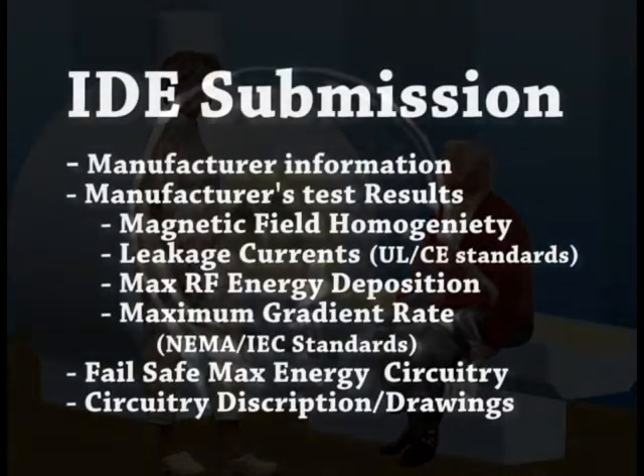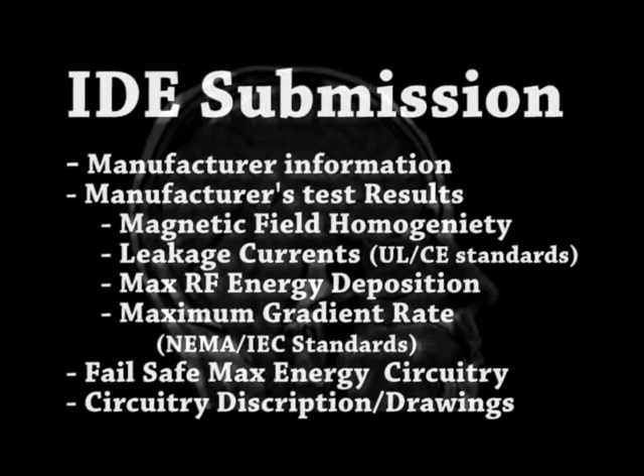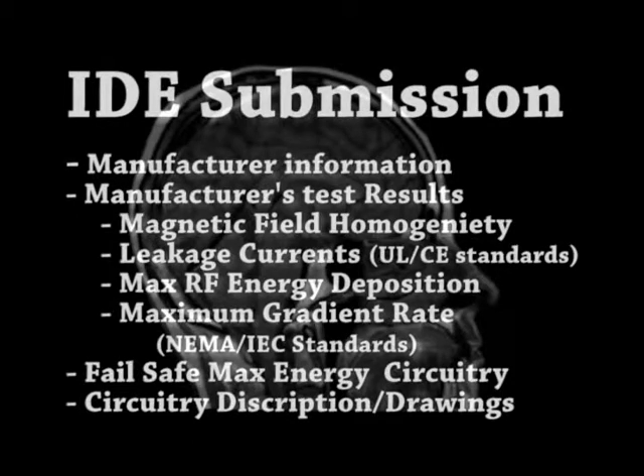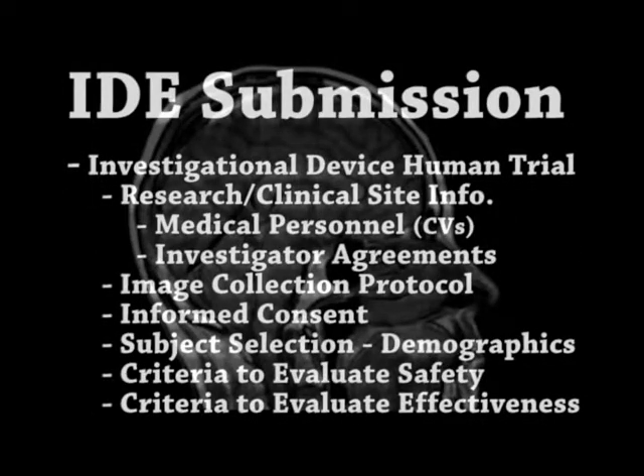Contained in the IDE submission to the FDA is information about the manufacturer with all the manufacturer's test results documented following UL and CE mechanical and electrical safety standards, such as pinch points and leakage currents. NEMA and IEC magnetic resonance energy exposure testing protocols and energy limitation standards for magnetic resonance devices are also tested and included. These energies include magnetic field, radio frequency deposition, and rate of change of magnetic field. Circuitry that ensures fail-safe energy limitations must be documented with descriptions and circuit drawings. Complete detail about the proposed human trial is documented.